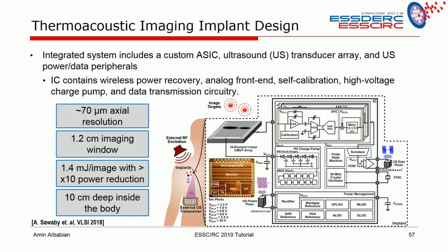This chip is a little bit more complicated compared to the other chips. So we need to have not only 16 receiver channels, but we need to calibrate these 16 receiver channels, because usually when we have ultrasonic systems, we have a lot of calibration phases with known transmits, with known pulses. Here we don't have any of those.